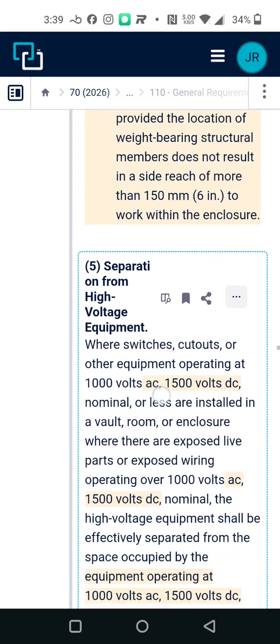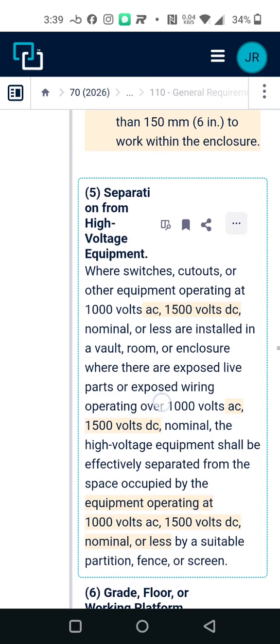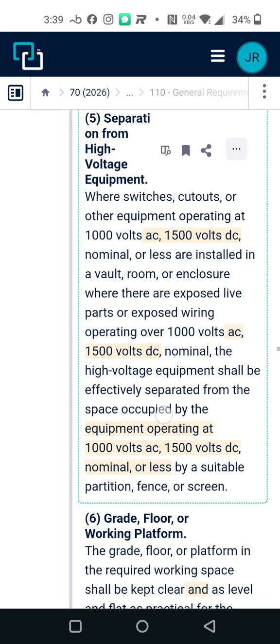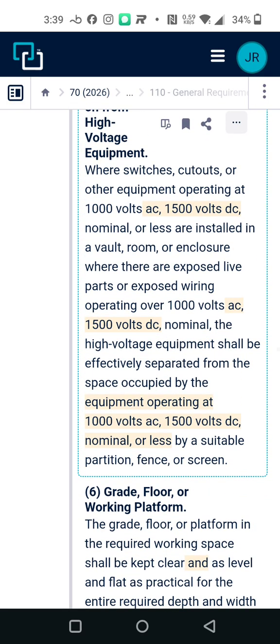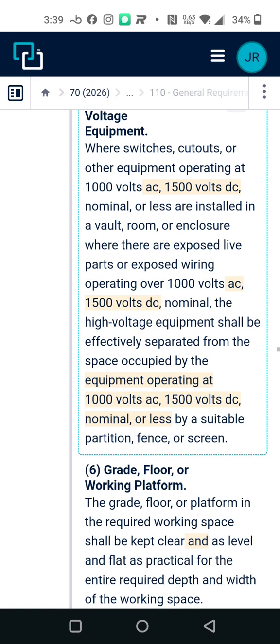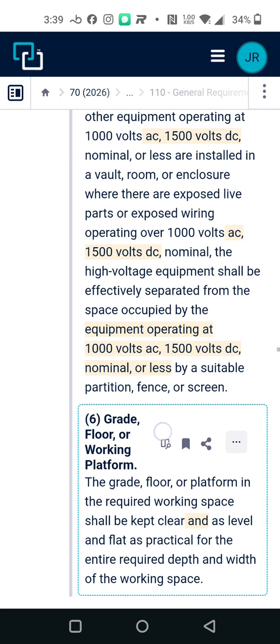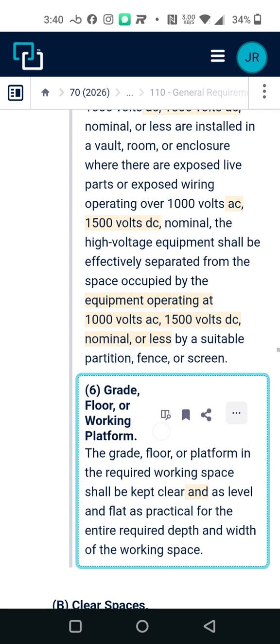Separation from high voltage equipment, where switches, cutouts, or other equipment operating at 1000 volts AC or 1500 volts DC nominal or less are installed in a vault or enclosure where there are exposed live parts or exposed wiring operating over 1000 volts AC or 1500 volts DC nominal. The high voltage equipment should be effectively separated from the space occupied by the equipment operating at 1000 volts AC, 1500 volts DC nominal or less by a suitable partition, fence, or screen.